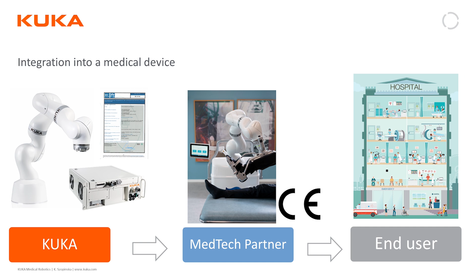The CB certificate is the world's first international system for mutual acceptance of product safety test reports and certificates. It's designed for electrical and electronic equipment, devices, and components. This means that we, on our side, can already carry out certain tests of the robot and in this document certify that the robot complies with certain regulatory requirements. This makes integration of the LBR Med into a medical device much easier, as tests don't have to be carried out twice by the medical device manufacturer. It saves costs and time for our customers and minimizes the risk of difficulties in the regulatory process.